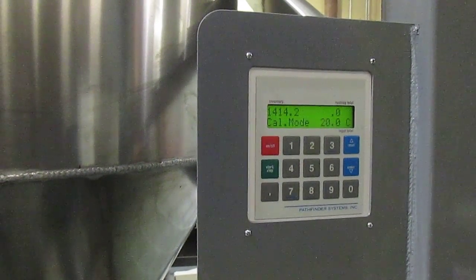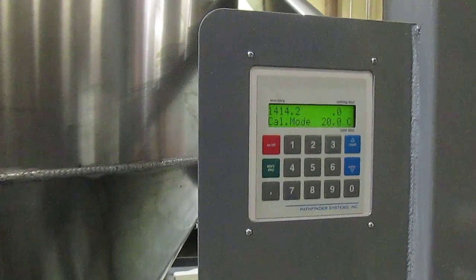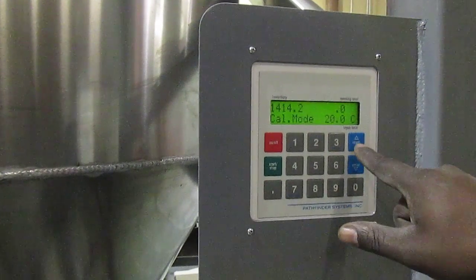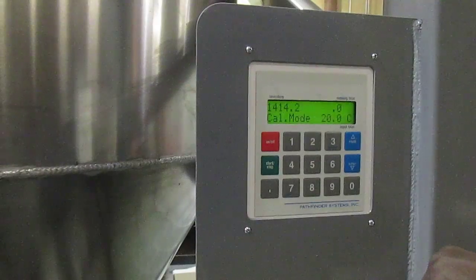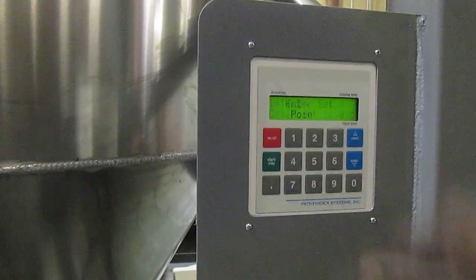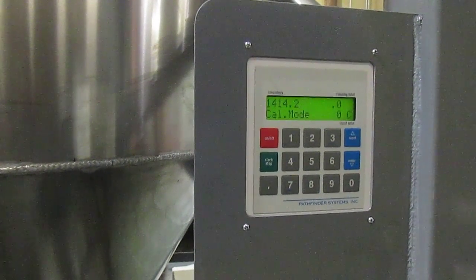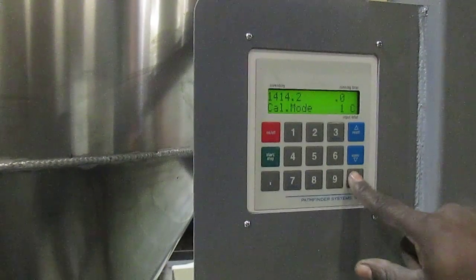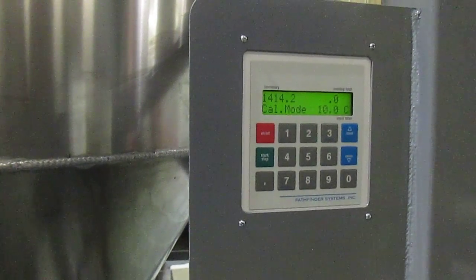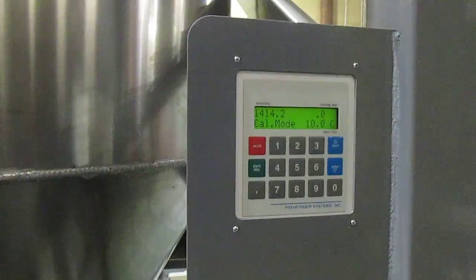We're going to calibrate this on a 10-pound run. I'll hit reset, and you'll notice it says 20 pounds. Now I'll hit reset again, and it says enter set point. I'll type in 10, then hit enter. At this point, I'm ready to go.